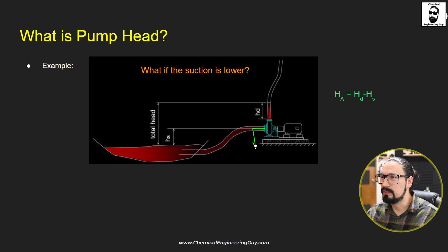But the discharge head will be lower, and that makes a lot of sense. Let's say this is -4. Then this must be 6. And if you add 4 plus 6, this equals the 10 value right here. This means you may not have enough pressure to run your devices.